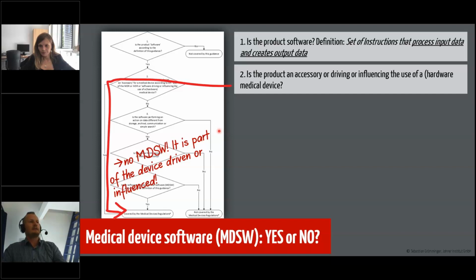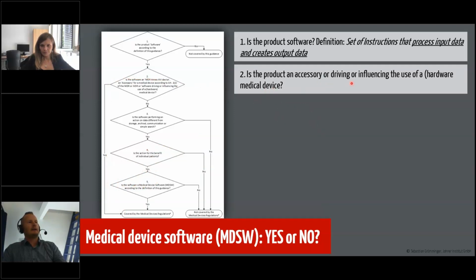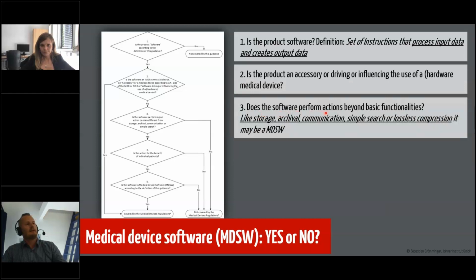However, be careful if the software does something additionally, like interpreting a result, then this would be a critical part which can upclassify the software. So if that's not the case, it's not driving or influencing the use of a hardware or other software device. The question is, does the software perform actions beyond basic functionalities? So here they mention clearly storage, archival, communication, or simple search or lossless compression is such a basic functionality which doesn't make the software an in vitro diagnostic product. So with this guidance, you have some arguments to get out of the IVDR for software that, for instance, just communicates the result from a reader device in a PDF format, for instance, to a computer. Then it's just a communication.